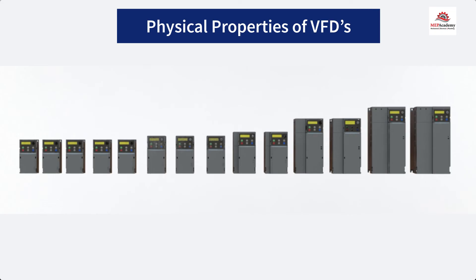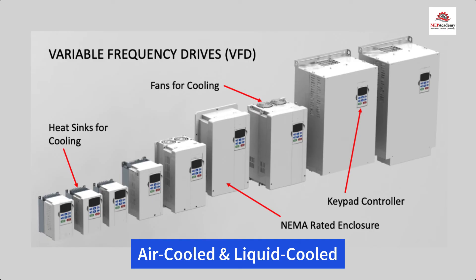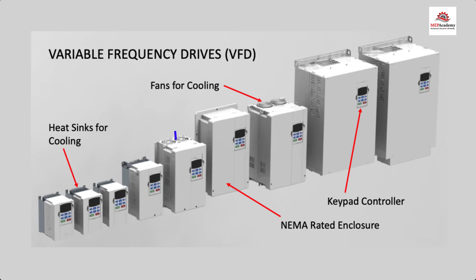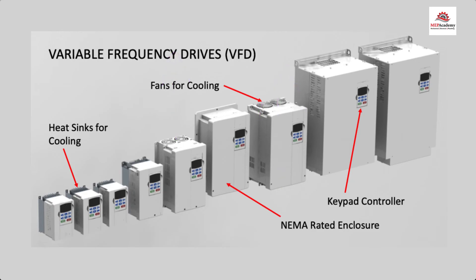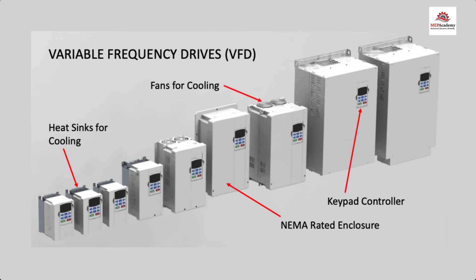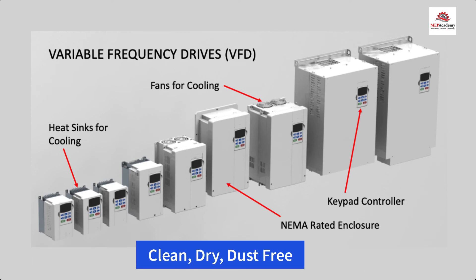VFD cooling requirements: there are two methods to keep variable frequency drives cool — air cooled or liquid cooled. Liquid cooled is used on larger VFDs, so most likely you'll be dealing with air cooled, or it'll just have a heat sink. Cooling is required to remove heat from the semiconductors and ancillary devices within the VFD. VFDs require space around them for the proper flow of air through the cabinet. Be sure to check the mounting instructions to avoid overheating and causing premature failure. Small VFDs require anywhere from 40 CFM to over 1,000 CFM for larger drives. Check the drive manufacturer's requirements for space around the drive. The area around the air-cooled VFD should be kept clean, dry, and free of dust.